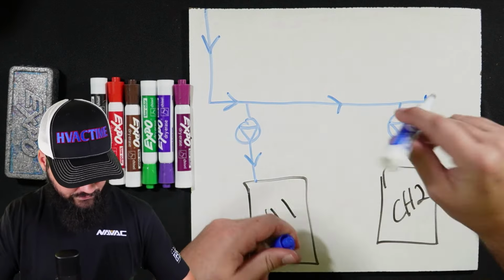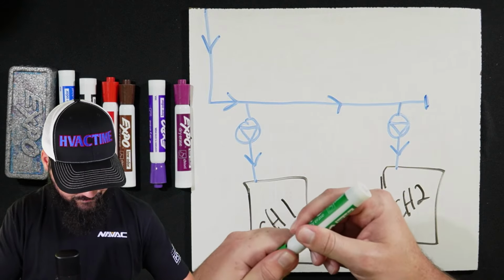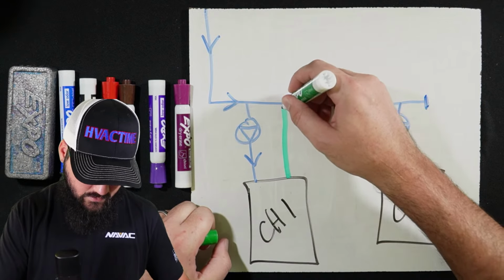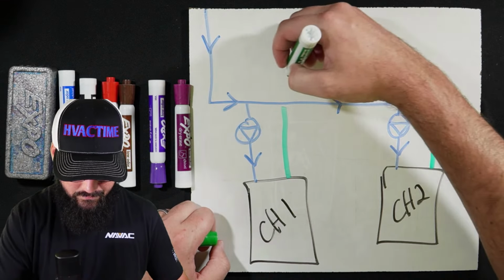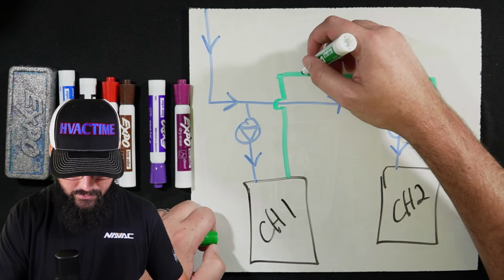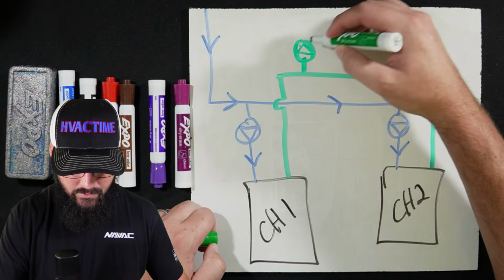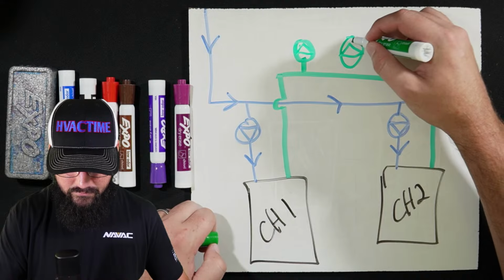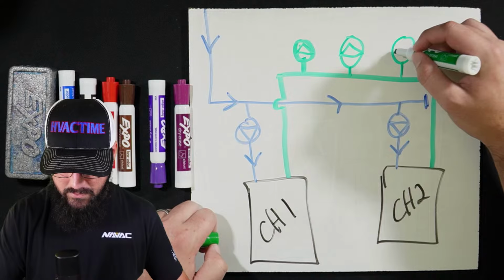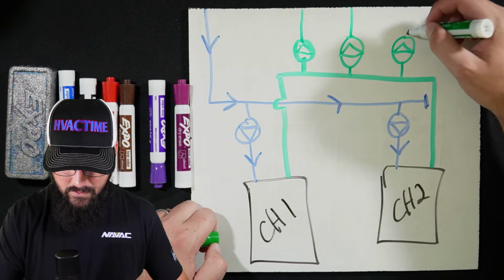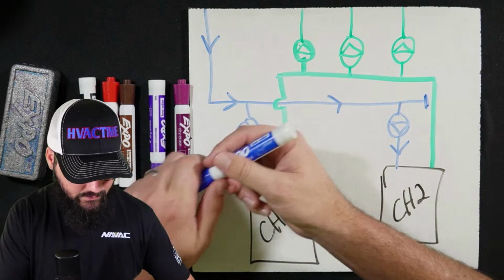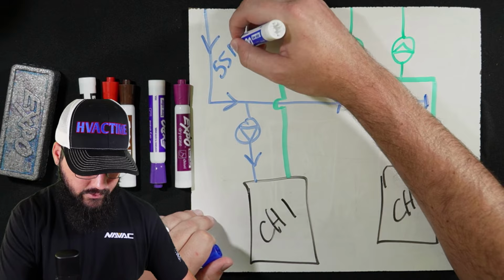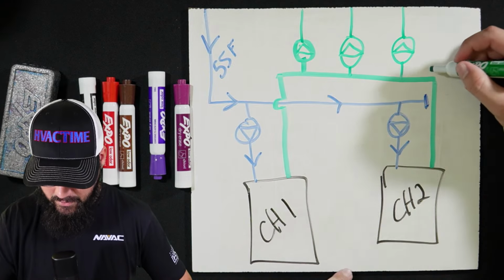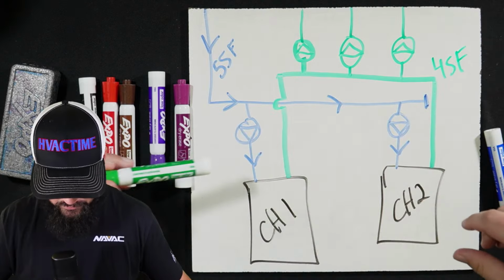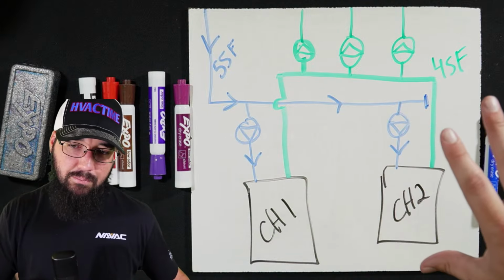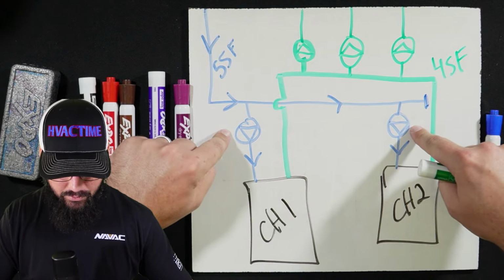Now, this will leave as chilled water, and we will go to another header with another set of pumps. We could have however many pumps here. Let's just say this is 55-degree Fahrenheit water coming in. Chillers are ideally outputting, say, 45 in this case, whatever the case may be, it depends on your loop. This is our basic plant layout of what this plant should look like. These are your primaries, these are your secondaries.